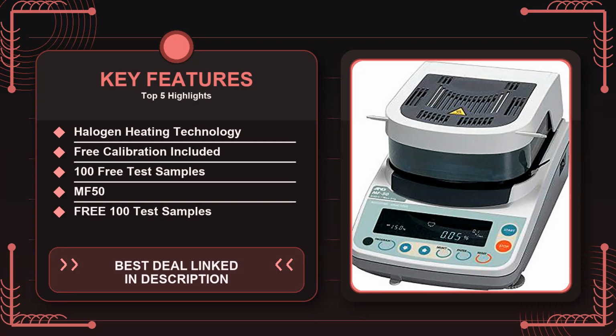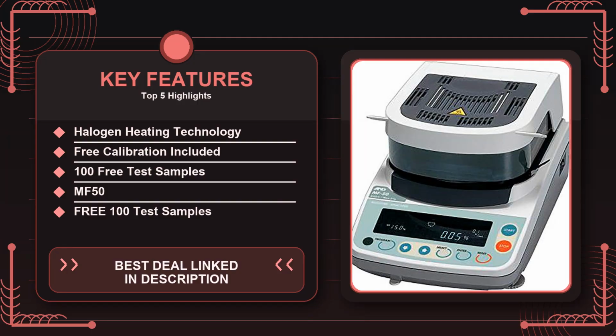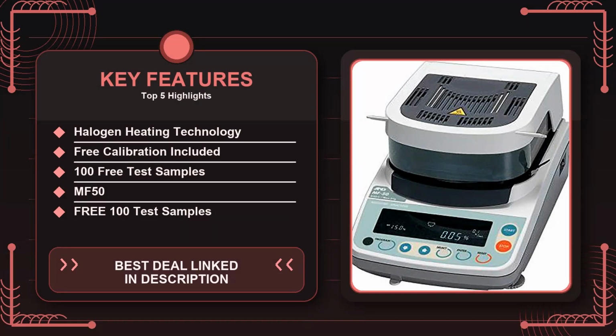It's not a fatal flaw, but it does mean you need to understand the nature of your material before you hit start. Another practical weakness is the limited capacity for continuous operation. The MF50 will automatically shut off after a predefined idle period to protect the heating element, which is a sensible safety feature but can be inconvenient if you're running a marathon testing session. You'll need to restart the machine and recalibrate the scale if the shutdown occurs mid-run, which adds a small pause to your workflow.